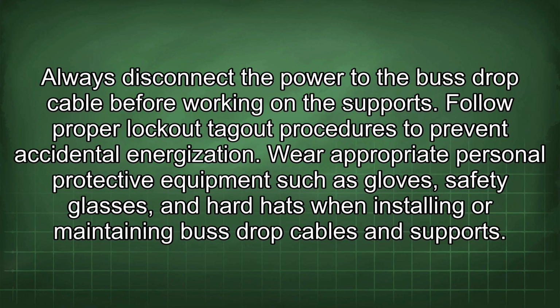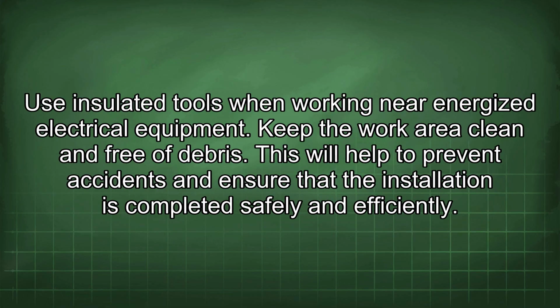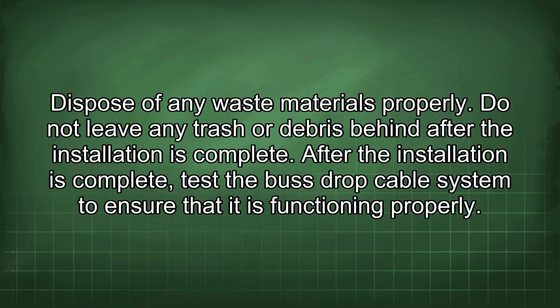Always disconnect the power to the bus drop cable before working on the supports. Follow proper lockout-tagout procedures to prevent accidental energization. Wear appropriate personal protective equipment such as gloves, safety glasses, and hard hats when installing or maintaining bus drop cables and supports. Use insulated tools when working near energized electrical equipment. Keep the work area clean and free of debris. This will help to prevent accidents and ensure that the installation is completed safely and efficiently. Dispose of any waste materials properly. Do not leave any trash or debris behind after the installation is complete.